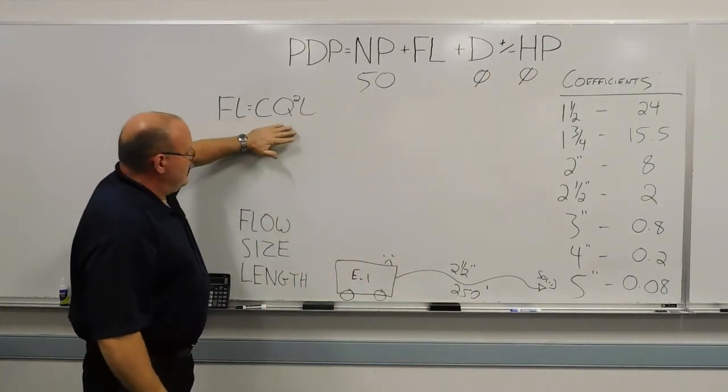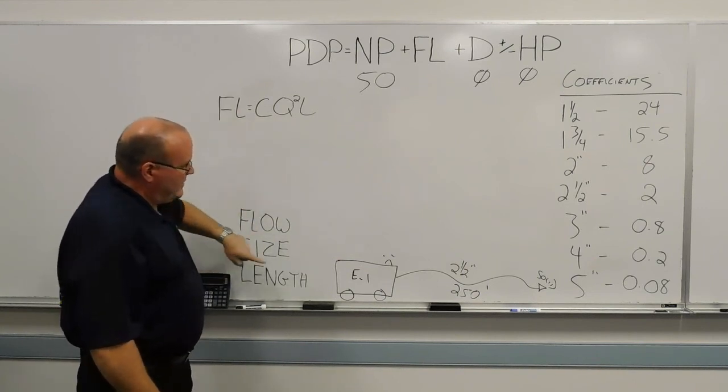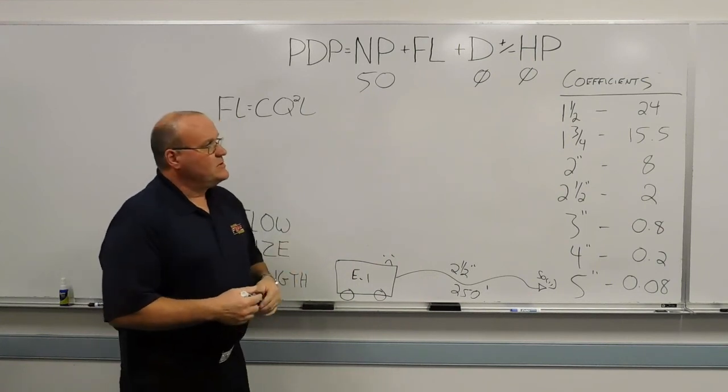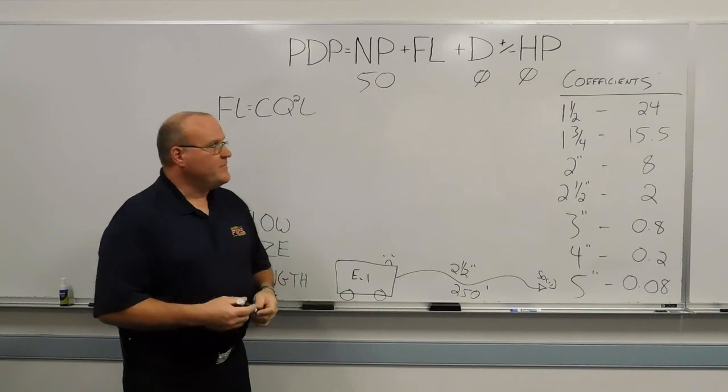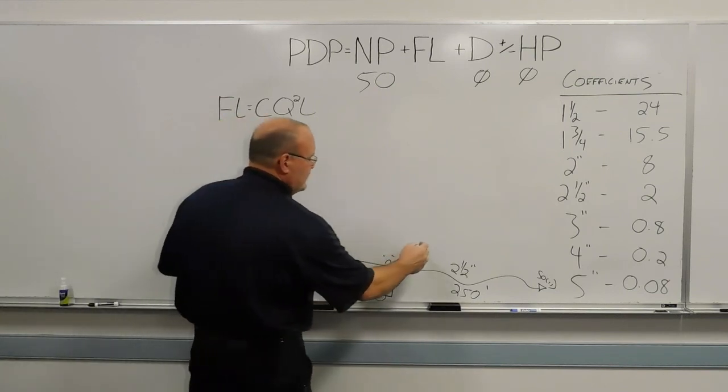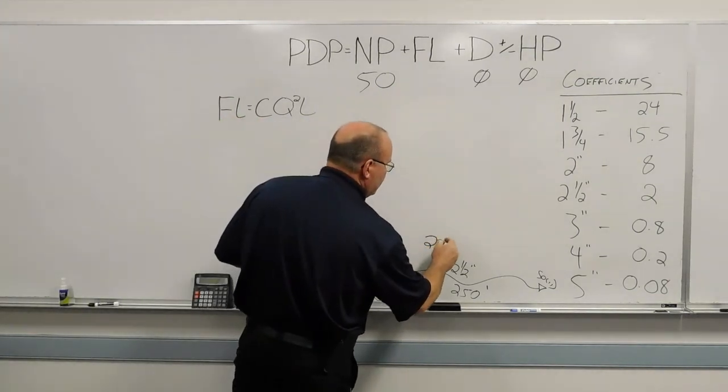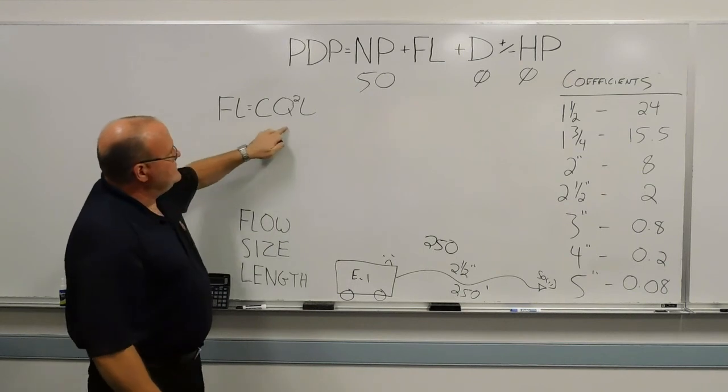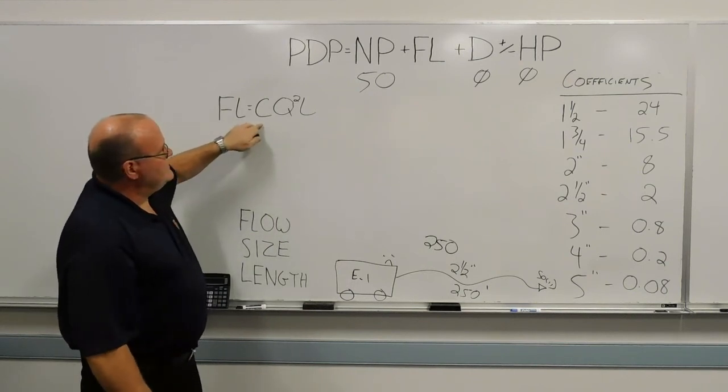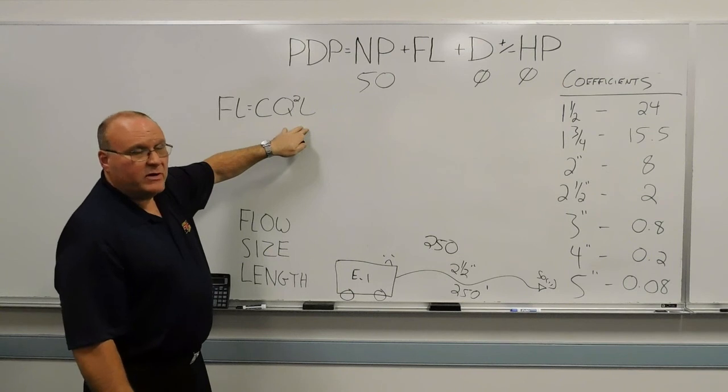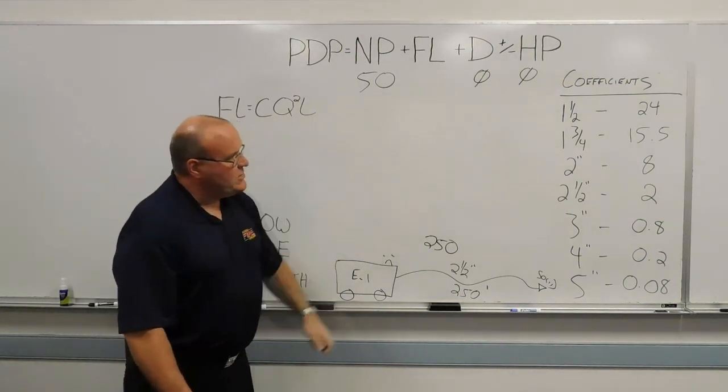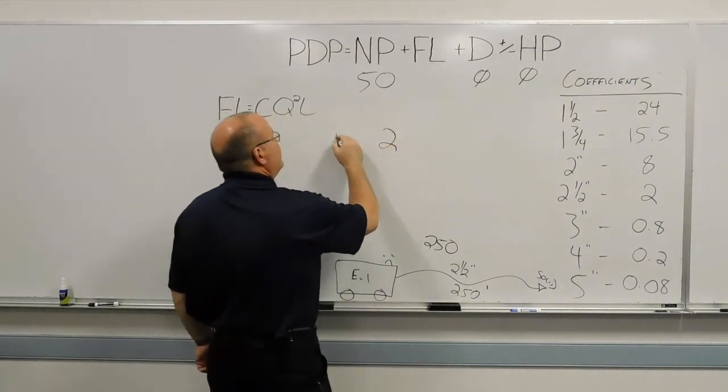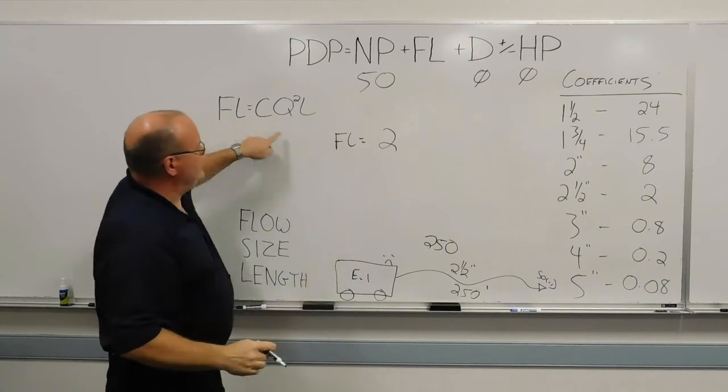So, CQ²L, flow size and length. So the flow on our 250 foot, two-and-a-half-inch hose line, we're going to use a number of 250 gallons a minute. So the flow, 250 gallons a minute. The size of hose, two-and-a-half, and the length, 250. So when we plug all these numbers in this formula, CQ²L and the Q and the L are divided by 100. So the C coefficient for two-and-a-half-inch hose is two. So FL equals the C is two.